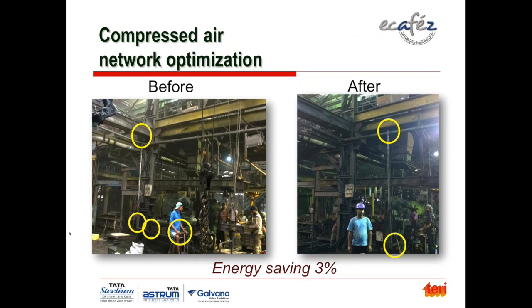So by optimizing or reducing the bends in the pipeline, a very simple measure, one can reduce the pressure drop across the pipeline. In this case, it could reduce the pressure drop at 2 or 3 places by half a bar. A half a bar reduction in pressure translates into about 3% saving of the compressed air energy.